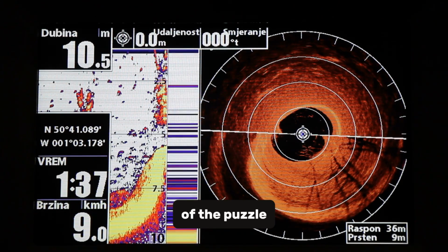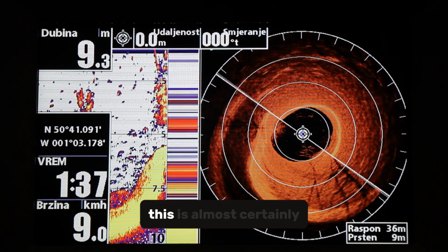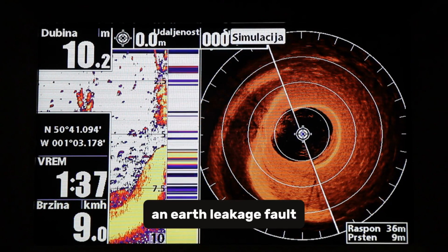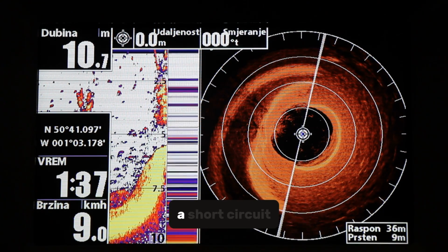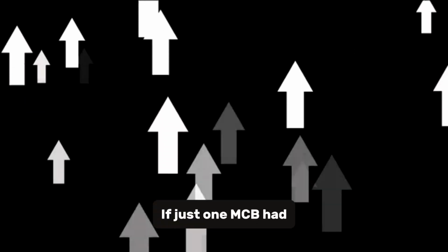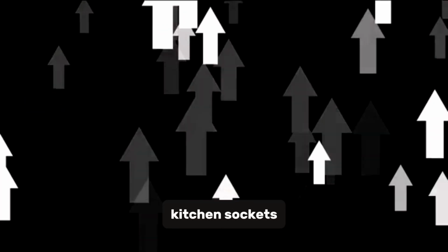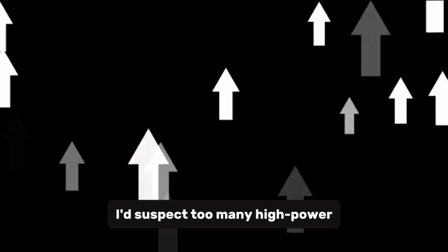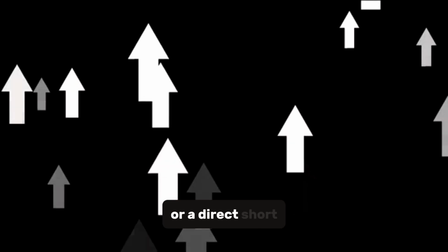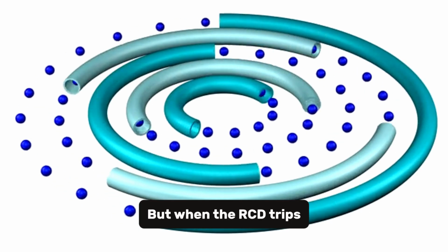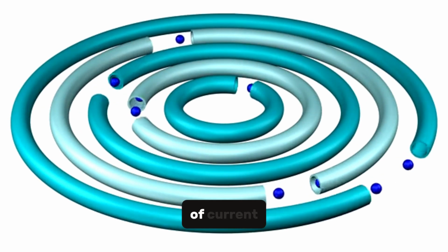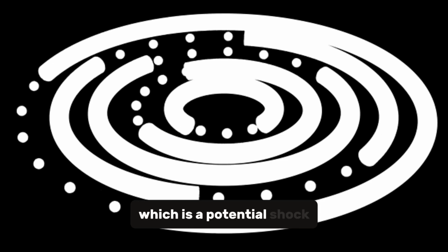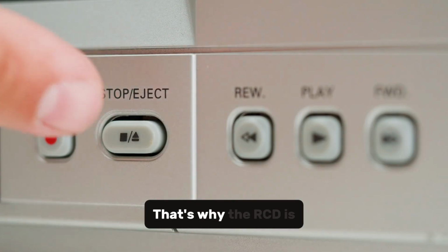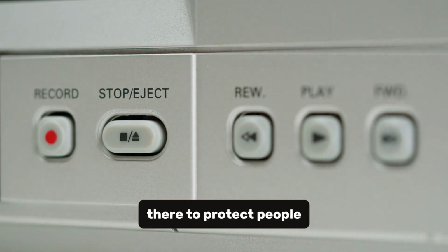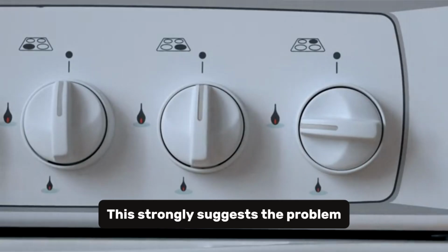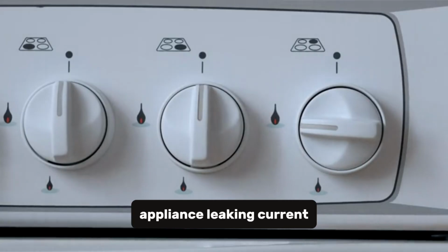This is a huge piece of the puzzle. It tells me that this is almost certainly an earth leakage fault, not a simple overload or a short circuit. If just one MCB had tripped, say the one for the kitchen sockets, I'd suspect too many high-power appliances were on at once, or a direct short. But when the RCD trips, it's detecting a tiny amount of current leaking to earth, which is a potential shock risk. That's why the RCD is there, to protect people. This strongly suggests the problem lies with a faulty appliance leaking current.